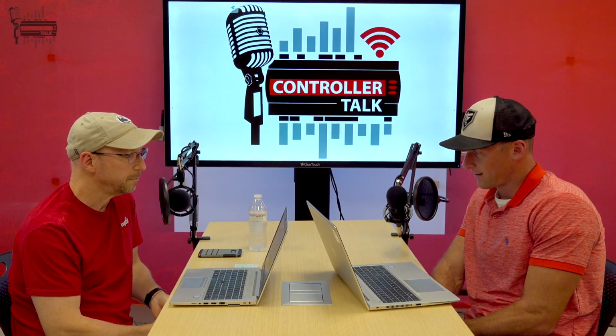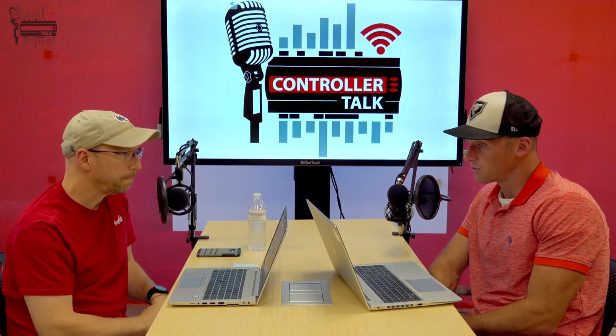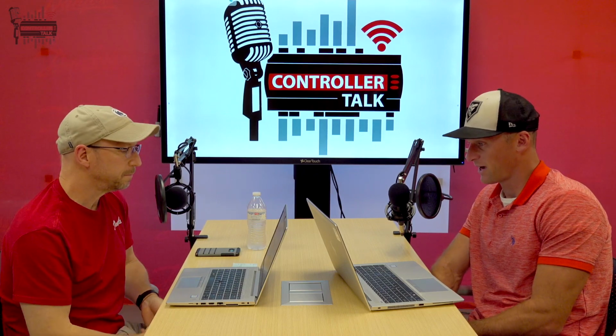And then another limit that I can't say I've ever even seen us get close to, but just to be made aware of, is that you can max out the total number of I/O points on the total package or total solution, if you take what's on the pack controller and then any other extension module attached to it. You can't go over 220 points. Yeah. Again, that's probably 2 or 3 times anything I've ever come across, but that limit is there too that we have to keep in mind. Yep, that's for the 782 and I believe the 781.